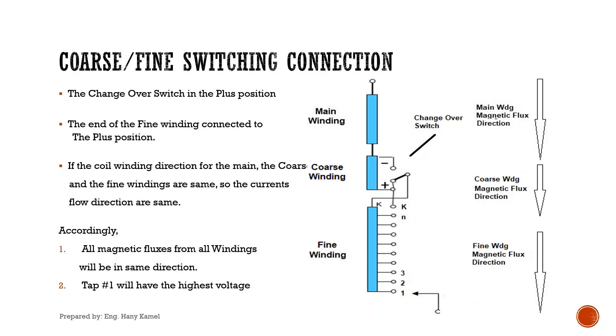For coarse-fine switching connection: if the changeover switch is in the plus position, the end of the fine winding is connected to the plus position. If the coil winding direction for the main, coarse, and fine windings are the same, the current flow directions are the same. Accordingly, all magnetic fluxes from all windings will be in the same direction. In this case, tap number 1 will have the highest voltage.